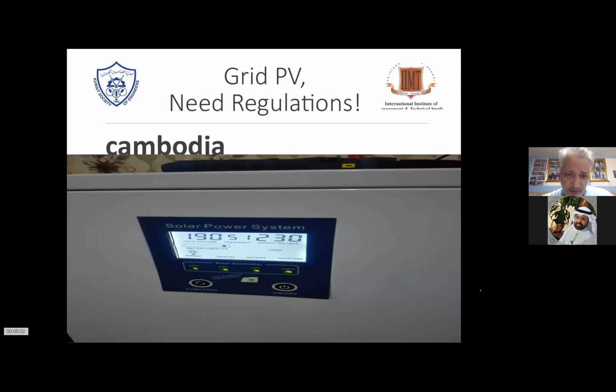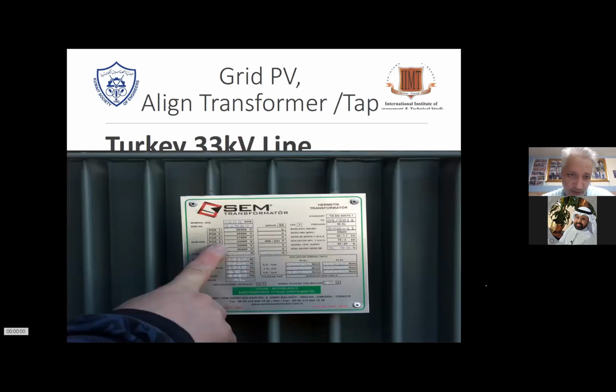Here in Cambodia, it's even worse. In some areas, it goes even down to 190 when there are lots of heavy loads supplied. So you need something like a line conditioner, or you use a hybrid system to actually use the batteries as a stable voltage. So you have 230 volts to begin with. That was in Turkey. This is a 33 kV, that's another system, 2014. So you can see the different settings, 6 of them. You can lower to 28.5 kV and up to 36 kV.